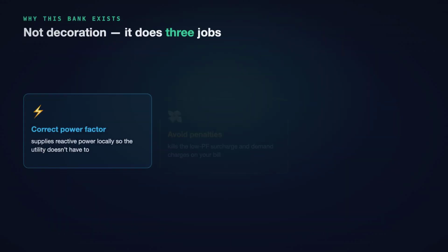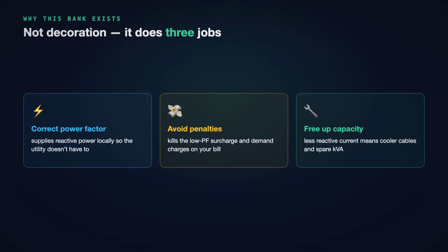Motors, transformers, and fluorescent gear all draw reactive power, current that does no useful work but still flows in your cables and still shows up on your bill. A power factor correction capacitor bank fixes that. It supplies that reactive power right at the load, locally, so the utility does not have to push it down the line. And it earns its place three ways.